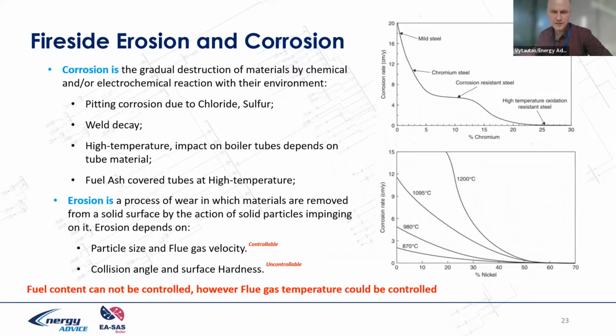There is a lot of discussion on erosion and corrosion, and typically misleading discussions could happen about erosion and corrosion effects. Corrosion is gradual destruction of materials by chemical or electrochemical action, like corrosion due to chloride or sulfur, and high temperature impact on tube material or ash covered tubes at high temperature. But mostly, from the pictures I have ever seen, it was the erosion effect. It is where material is removed from a solid surface by the action of solid particles. So erosion depends on particle size, when the fuel is not fully burned and the particle is big and goes through the tubes, and on flue gas velocity also.